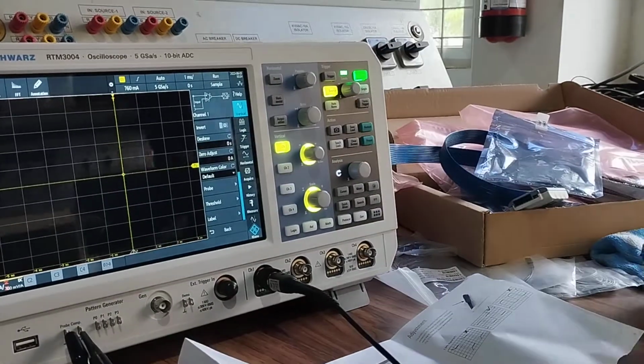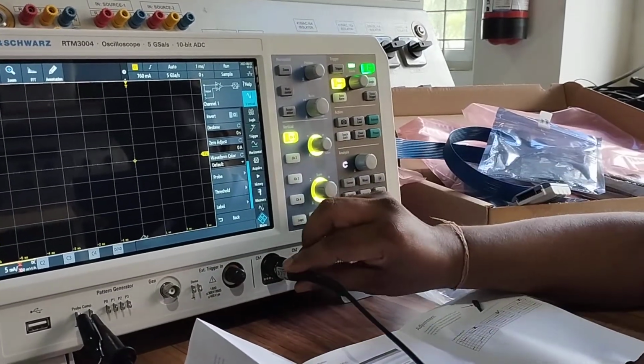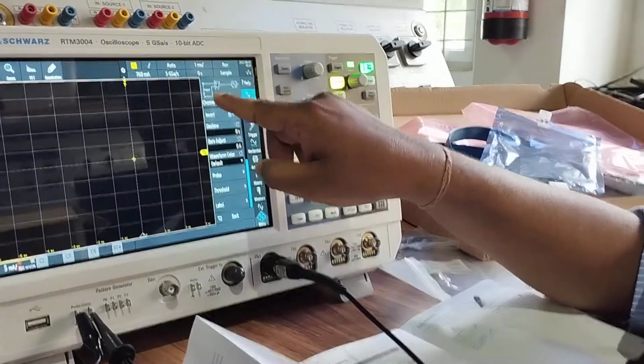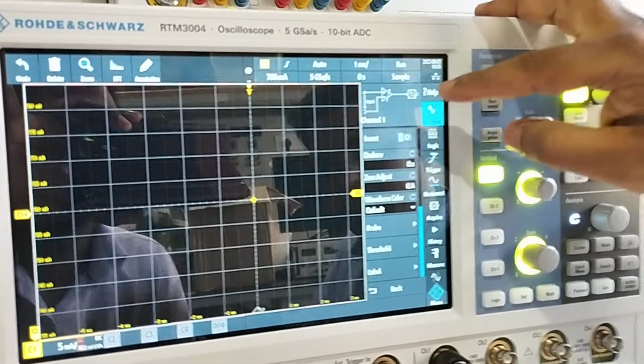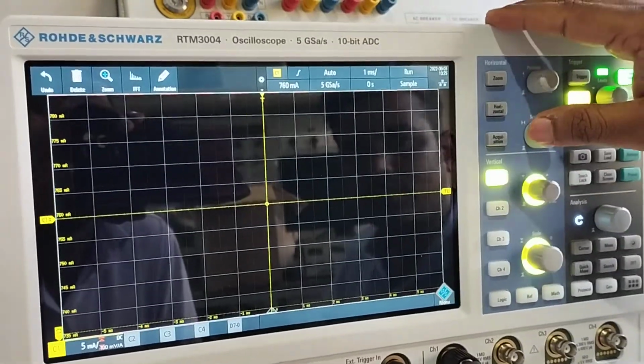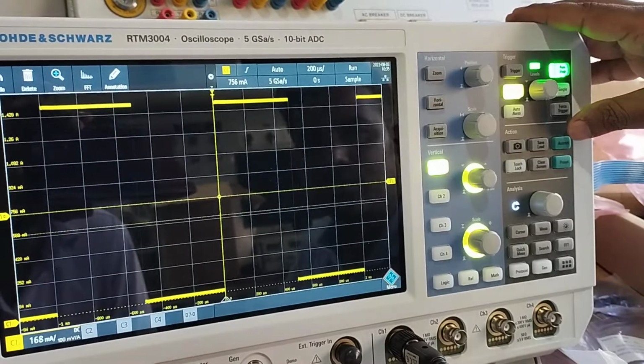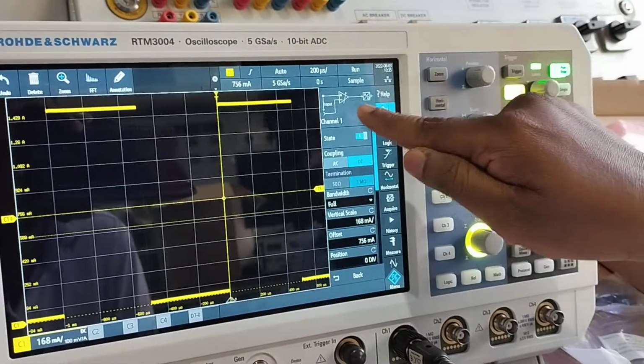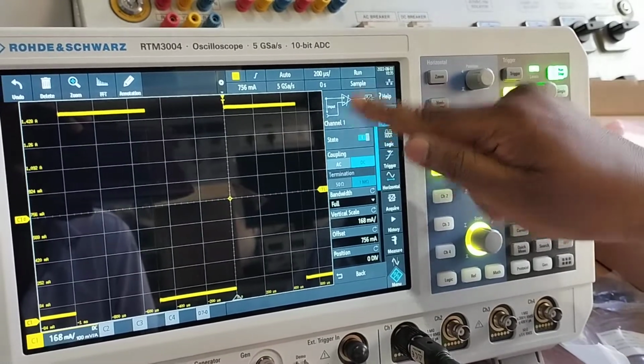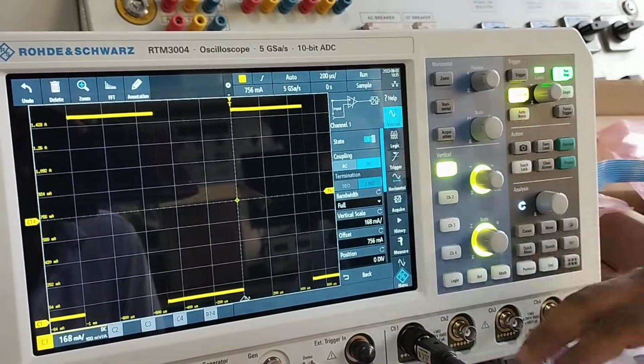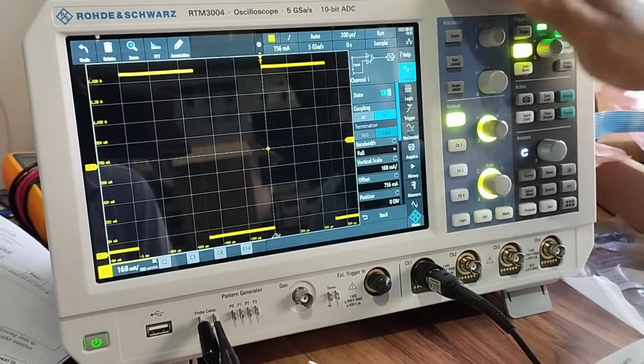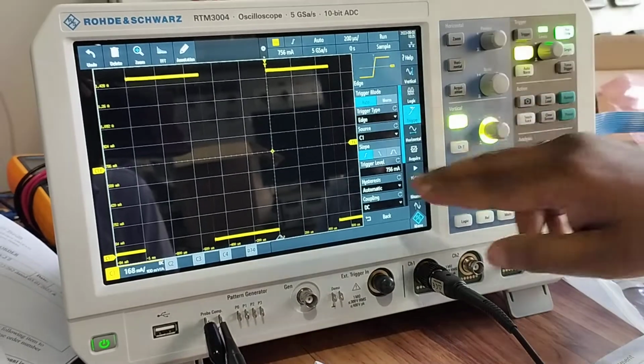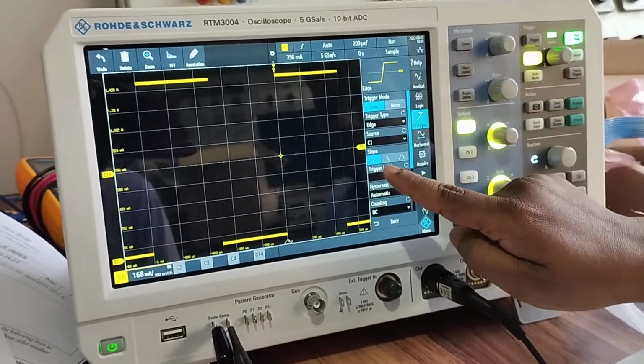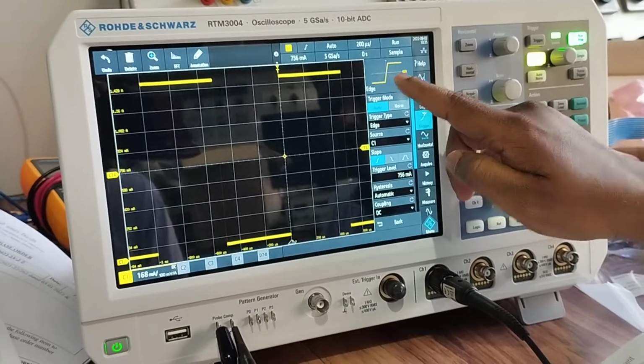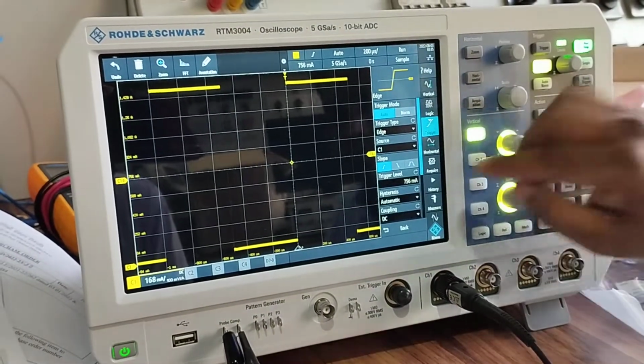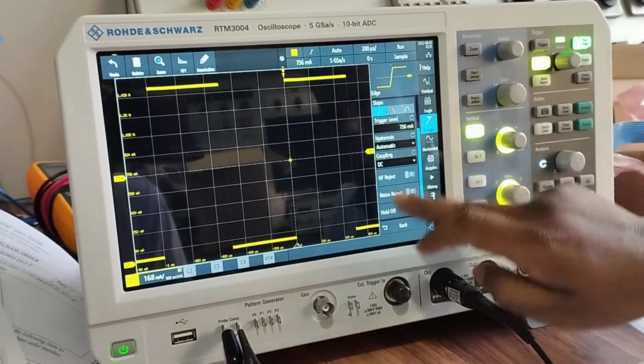In the vertical, I forgot to tell you one thing. Once you are feeding the signal, you can see the block diagram here, so how your signal is getting processed internally. So a fresh engineer also can easily understand how your signal is getting processed internally in the oscilloscope. Not only in vertical, in every stage you can see it. If you select the trigger, this is edge trigger, and your slope is rise time. So you can see where your trigger is, at which point your signal is getting triggered. So this is how the trigger level works.